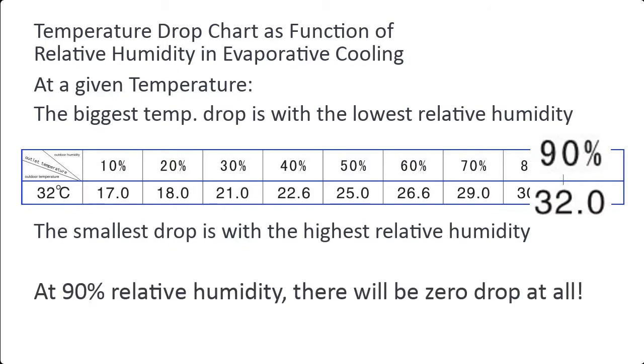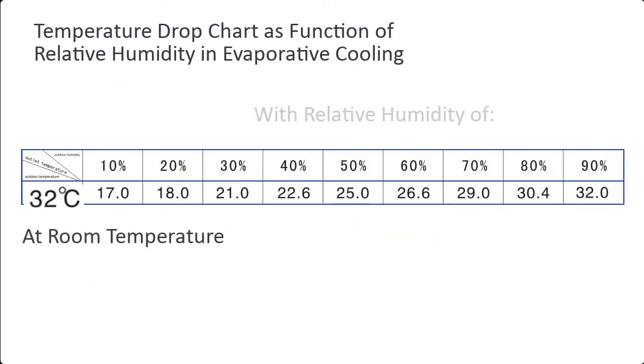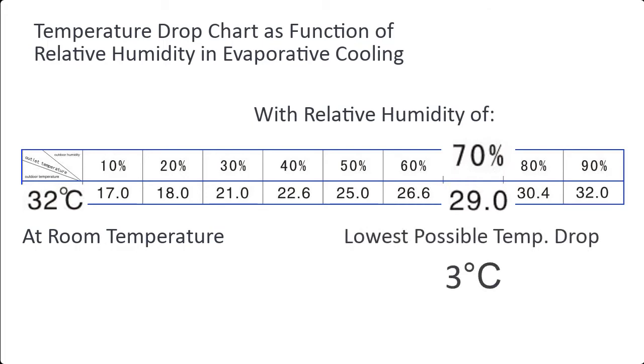At 90% relative humidity, there will be zero temperature drop at all. As shown by the thermometer, at 32°C with a relative humidity of 70%, the lowest possible temperature drop brings us to 29°C — only about 3 degrees.